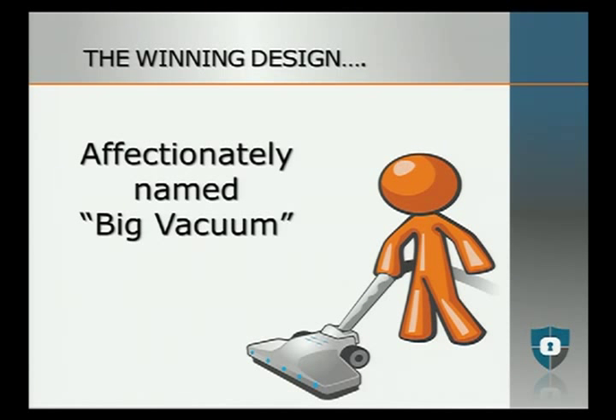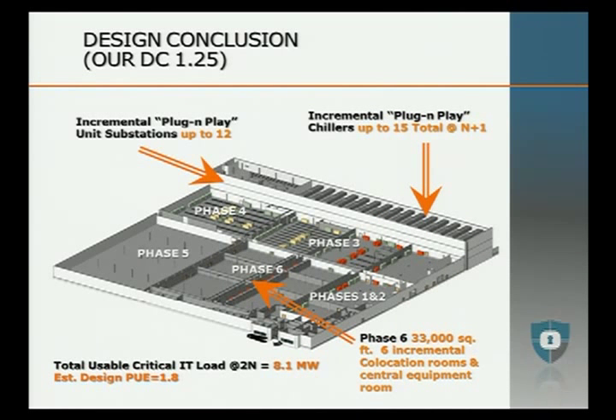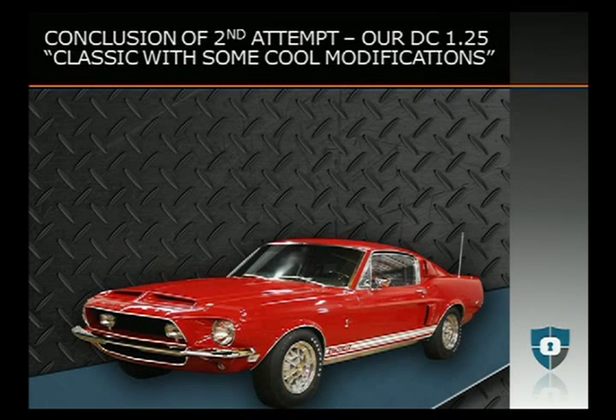At the end of it all, we came up with a design, and of course we had to have a nickname, so we called it the Big Vacuum. We had created, in phase 6, a central machinery corridor. We were going to do hot aisle containment, a floating hot air return plenum, and we were actually taking a significant bite out of our PUE. We estimated we'd get the design PUE from 2.2 down to at or near 1.8. So, as you might imagine, we called it our attempt at Data Center 1.25. It was really a classic model with some cool modifications.